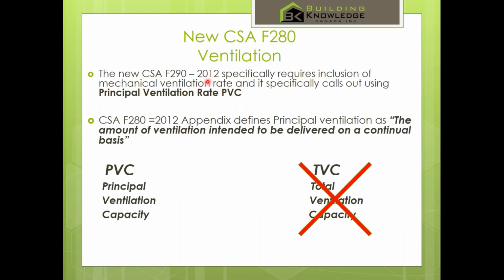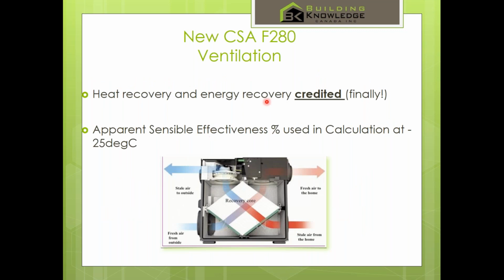One of the major changes in the new F280-2012 is that the recognition for ventilation is no longer for total ventilation capacity, which is what we've been sizing to in the past, but is now principal ventilation capacity. And that, by definition, is the ventilation that's intended to be delivered on a continual basis to a home. What this means is we used to be sizing homes based on 150 to, in some cases, 220 CFM total ventilation, range hoods, everything, and now we're only sizing to what's required as the principal. So that's a big difference. Heat recovery or energy recovery, ERVs or HRVs, are credited. So based on the ASE, not the SRE, but the apparent sensible effectiveness, we can include it in the calculation and get credit for it in our load calculations.